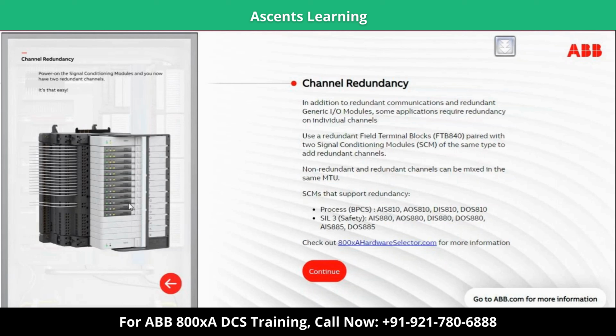In this case, you change the module and the back panel. Then you go to the hardware configuration settings in the control builder, and there you can assign the slot number and the channel number to this particular tag number. Then against this tag number, you can assign both of these, and it will get a redundant signal.